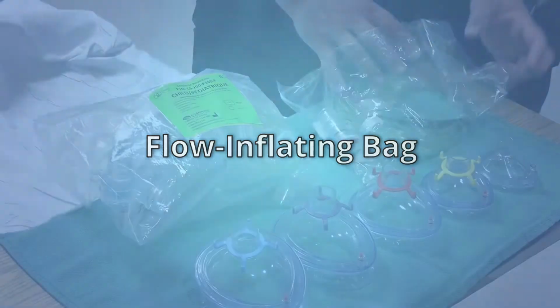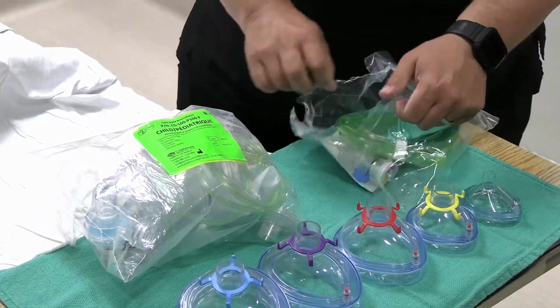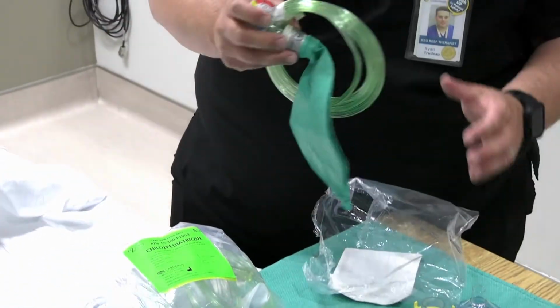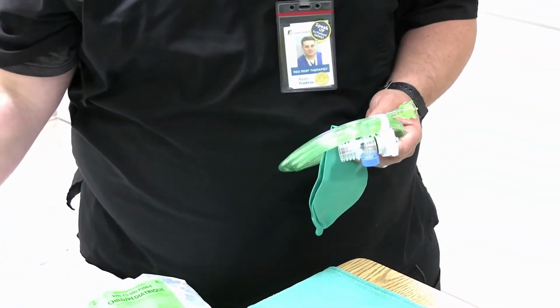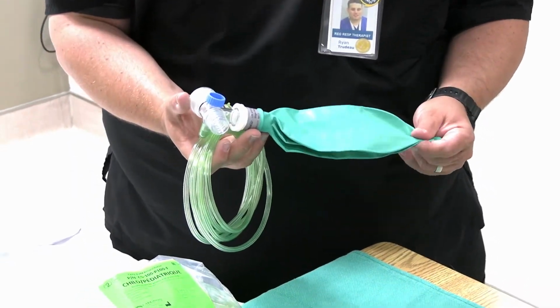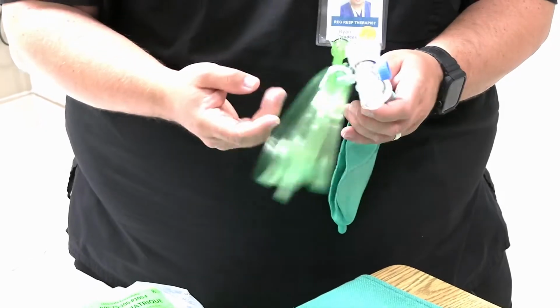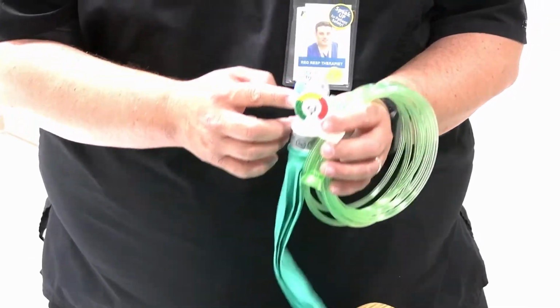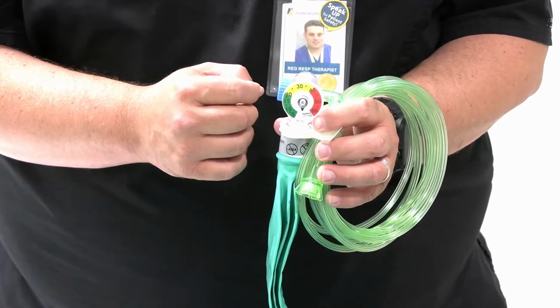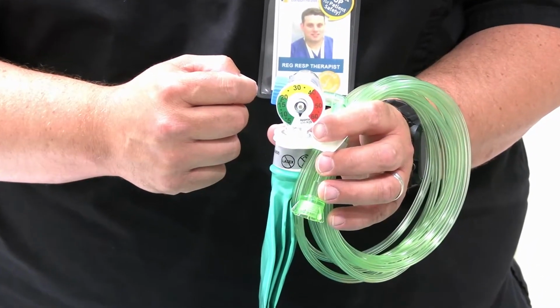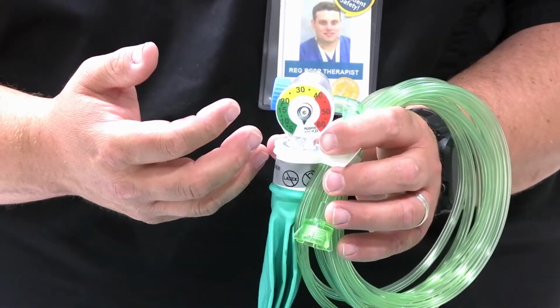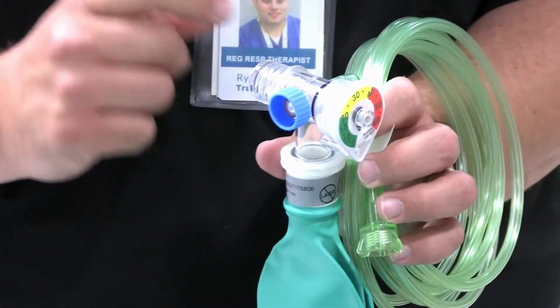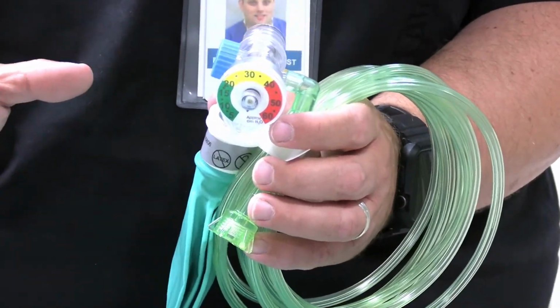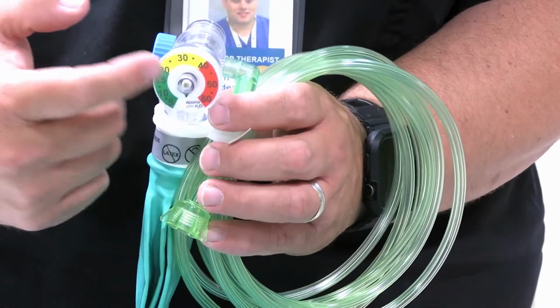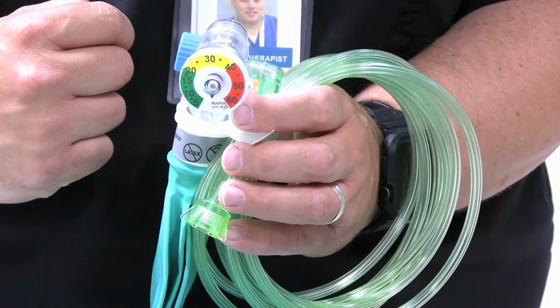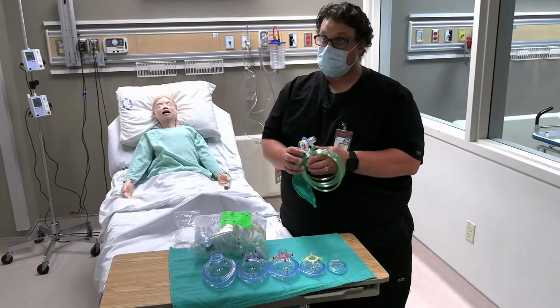So the first bag that I'm going to show you today is the flow-inflating bag. Now the flow-inflating bag requires a little bit more skill and experience than the self-inflating bag. But in the packaging, it comes with a gas reservoir here, oxygen tubing, and a manometer that will give you an idea of what pressures you're bagging your patient with. So you can set your PEEP level on this by using this blue dial here, and then depending on how hard and fast you squeeze the bag, it will generate a pressure in order to deliver the breath that way. Okay, so that is your flow inflating bag.